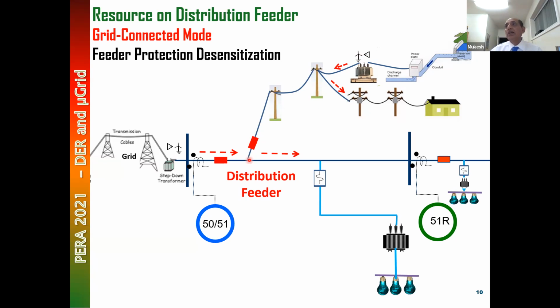Now, if you have a fault here, the current will come. Initially this resource is supplying power to the local load here, maybe supplying some power here, may or may not be. But once you have a short circuit here, the current will flow to the lowest resistance path, and current will flow from here, as well as short circuit current will come from here. Now, this recloser will see the current from this generator as well as the utility system. So it is going to see more current than before.